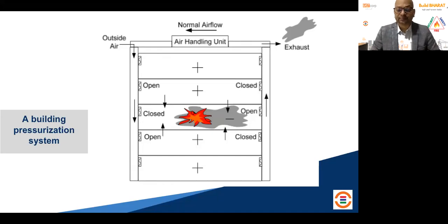Now, when you have this kind of system, which is typically a temperature controlled HVAC system, and that too with AHU control systems, you need to see that your smoke dampers do their job effectively, so that they open the return path and close the supply path. Why is it required? Because the moment you close the supply path, you are restricting the oxygen from coming in. You are restricting the air from coming in so that the fire doesn't propagate. And where does it come from? Fire science, the fire triangle. Oxygen is one element, right? We have studied it. So we are disconnecting that air supply. That means we are restricting the fire itself. It's a passive way, but this is passive by mechanical means.